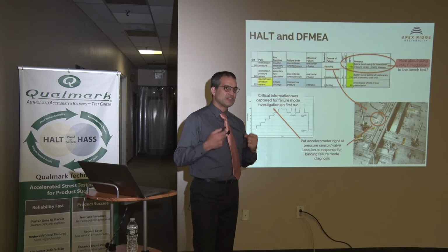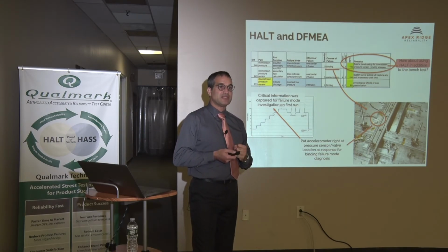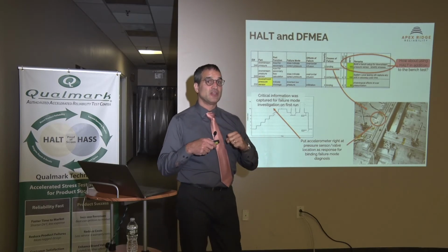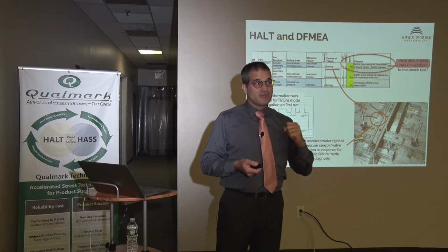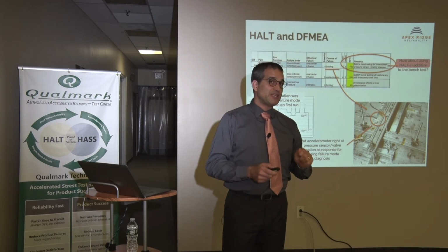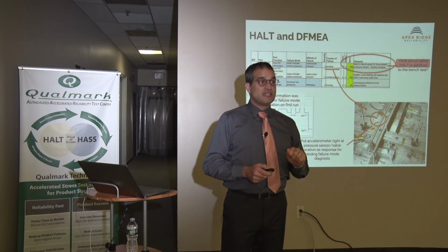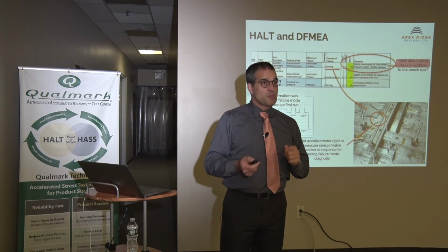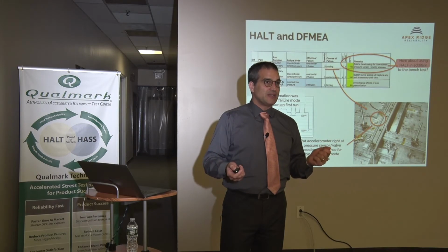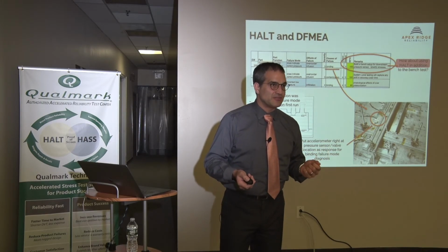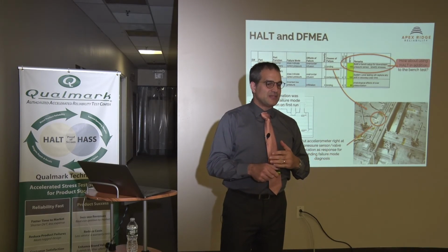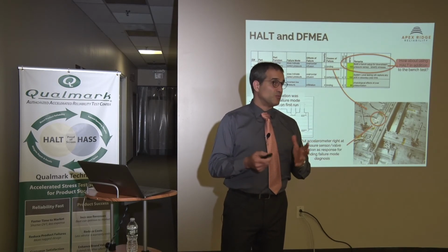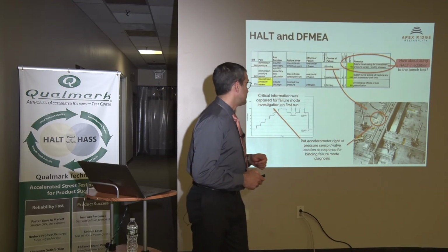What about if we take the sensor and find every possible failure mode and the parts around it? Where are the sensitivities that could be affected by manufacturing or use? Again, medical devices with patient interaction, extremely difficult issues for defining use case and environment for a reliability engineer. Why? Everybody's different. Every doctor's different, right? And it becomes very difficult to characterize.